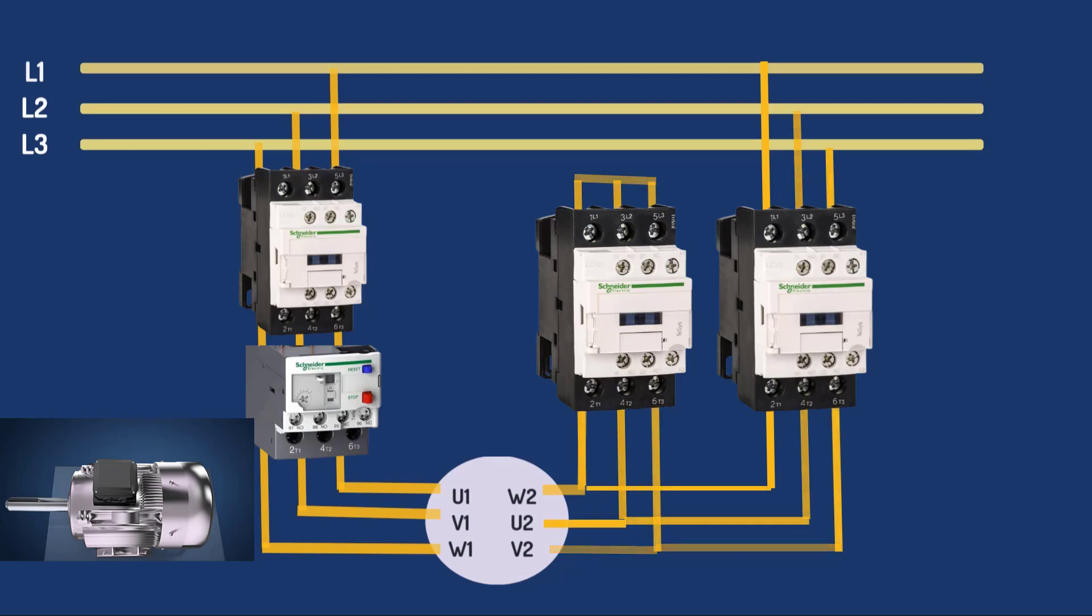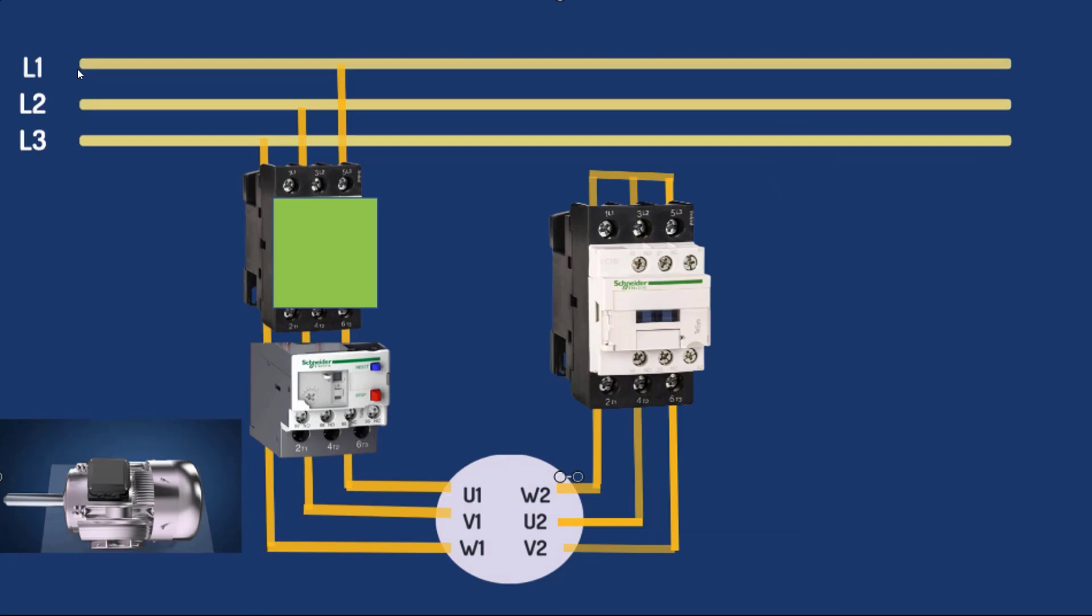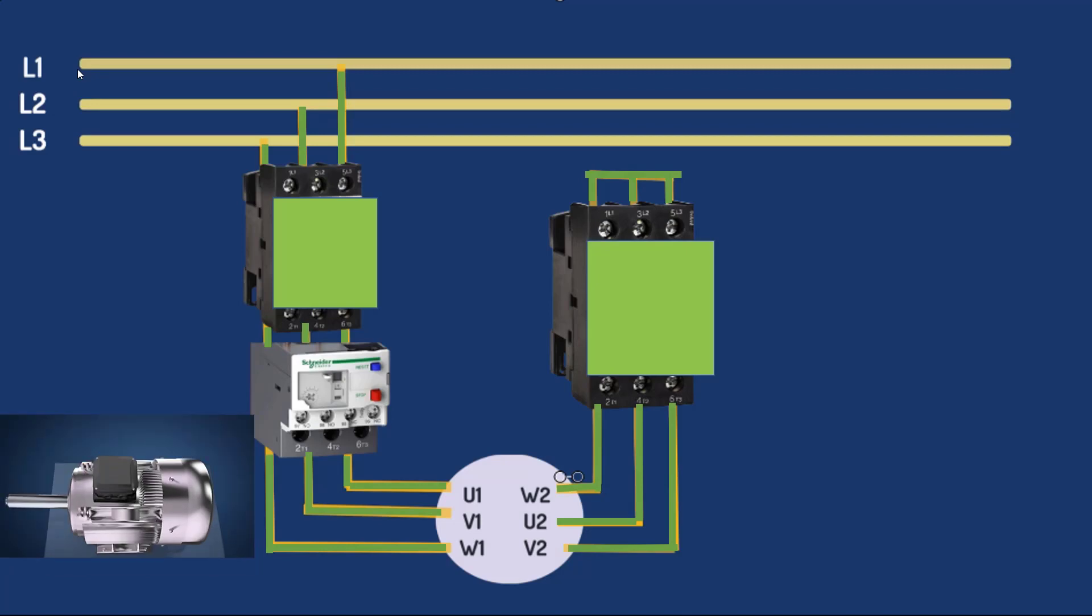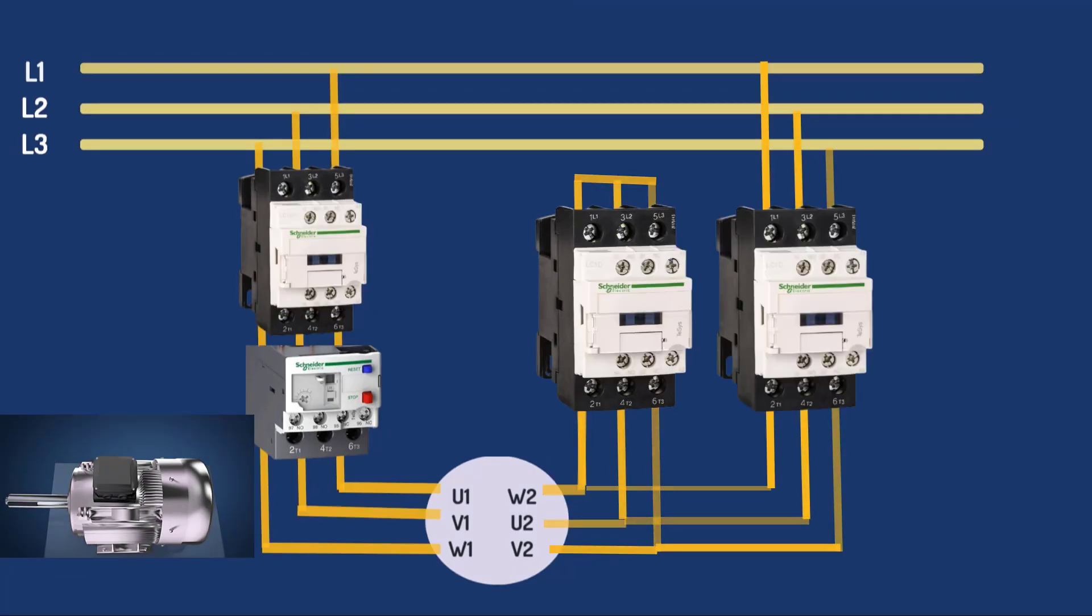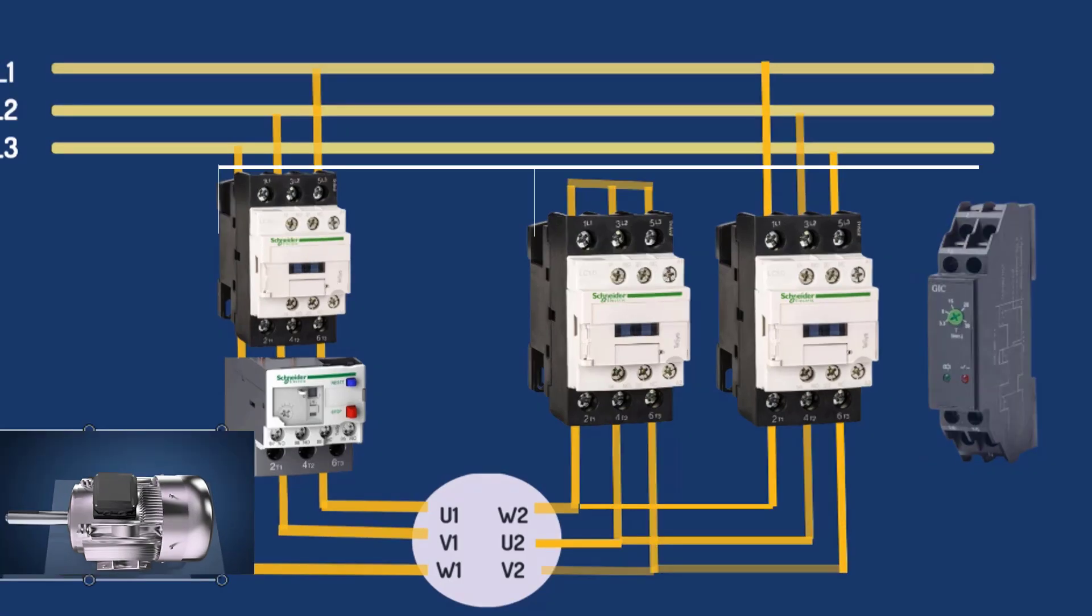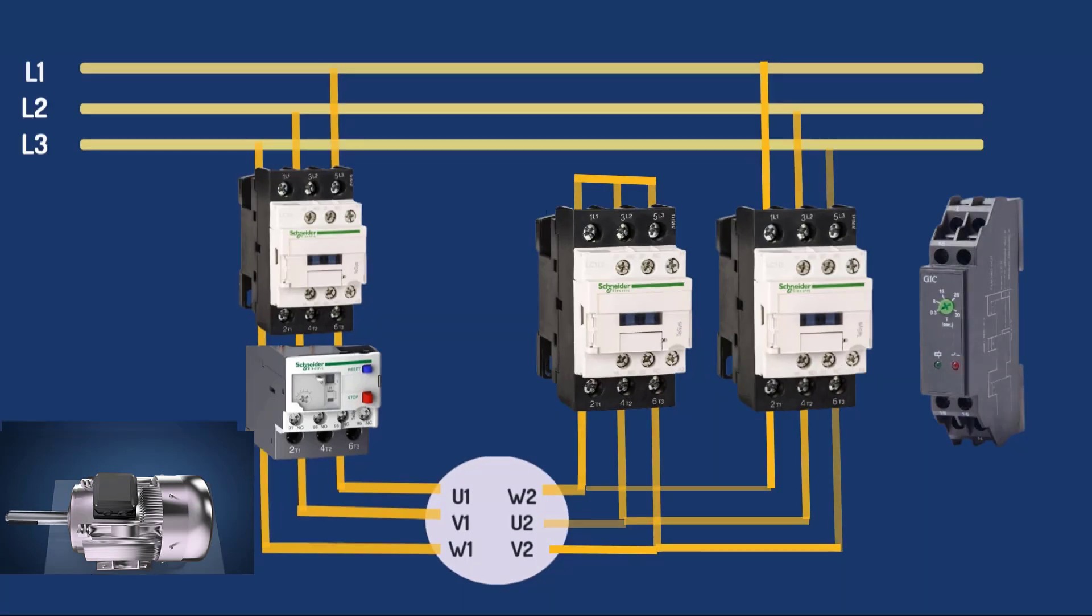Let's now understand the sequence of a star delta starter. Initially, your main and star contactors would be activated. At this point, your motor would be running in star connection. To control the transition from star to delta contactors, we would use a timer. Initially, when the motor starts running in star connection, the timer would start timing.